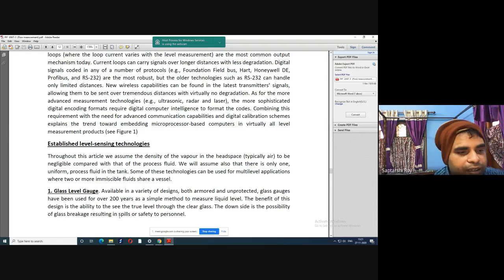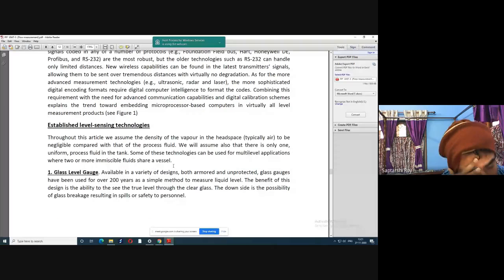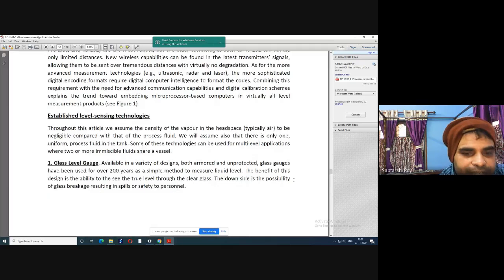Number one, glass level gauge. Available in a variety of designs, armored and unprotected glass gauges have been used for over 200 years as a simple method to measure the liquid level. The benefit of the design is the ability to see the true level through the clear glass. You can see clearly through the glass, and there is nothing complex in it. The downside is the possibility of glass breakage, resulting in spills and a safety risk to personnel.